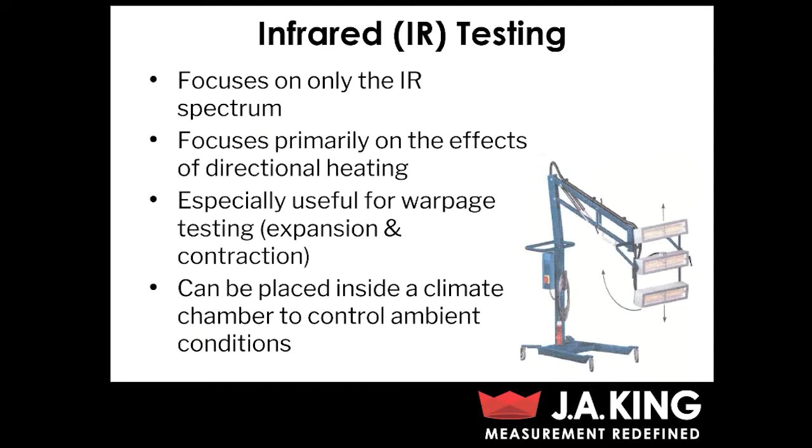And then also an infrared tester, typically, including the ones that we have in our lab, can be placed inside an actual climate chamber too. So you can control your ambient temperature and humidity, and then also have a radiant heat source.